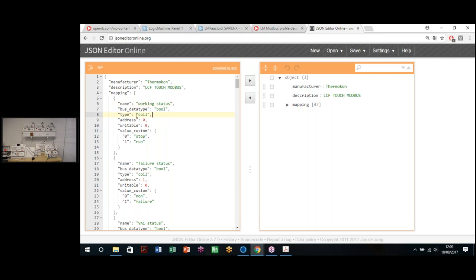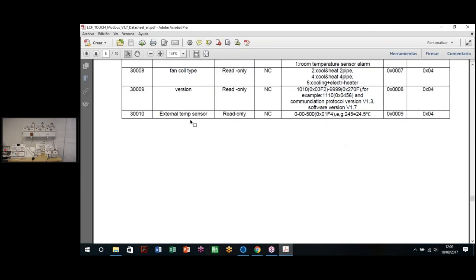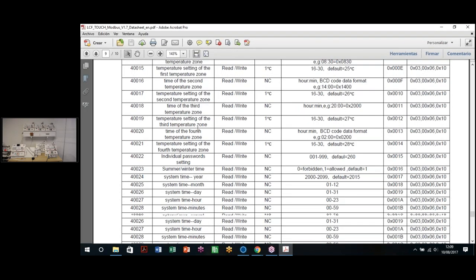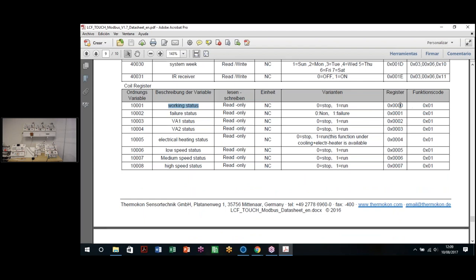In this case, we can see that we have a coil type register named working status, with the address at zero. So if we go to the user manual and we go to the coil registers, here we can see we have working status, and the address of the register is 000. We have to be very careful with this address. Some user manuals state at the top that all the addresses start at zero, but they reflect it in the table as if they start at one. So we have to be careful in which address we are starting.